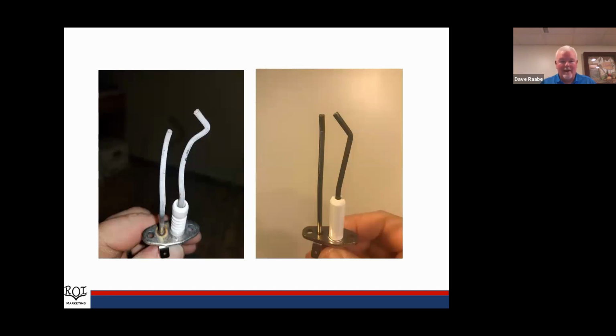Now, I talked about spark gap a little bit. So here's a picture of an electrode. The one on the left actually came out of a fairly new boiler. It was in about 2 months. The boiler was running on propane, and I happened to go out there, and the customer had never set it up with a combustion analyzer.